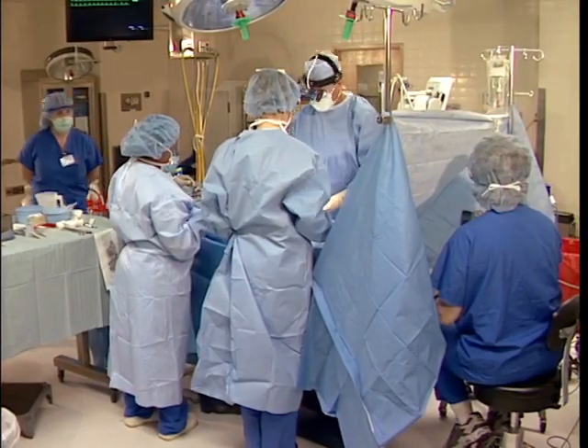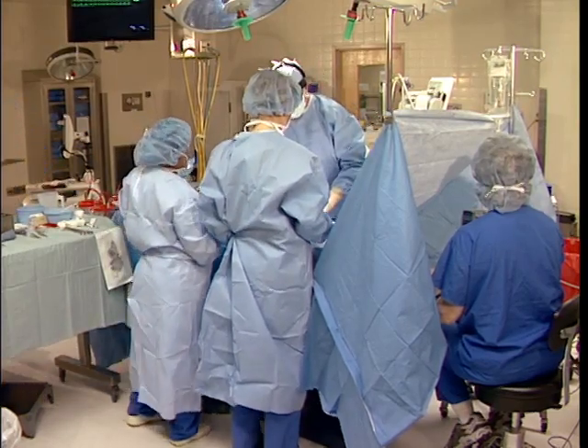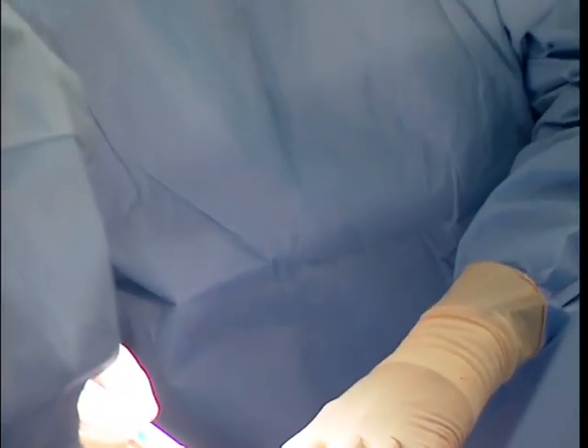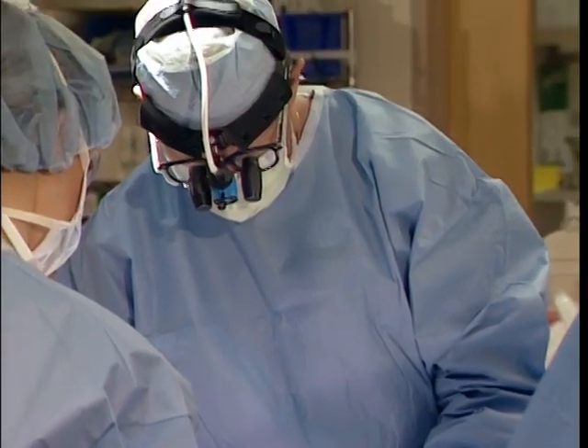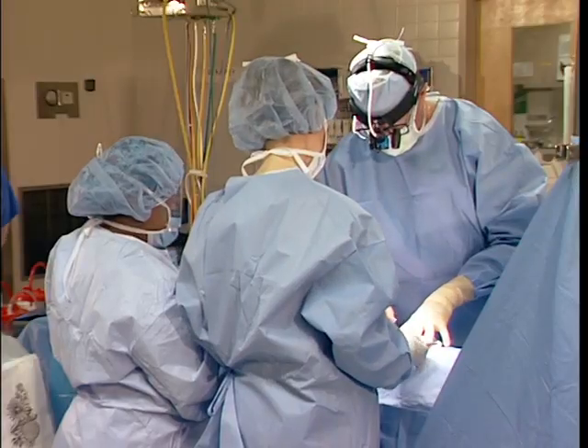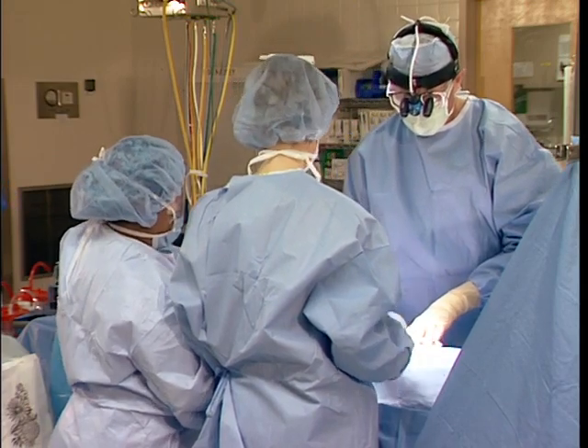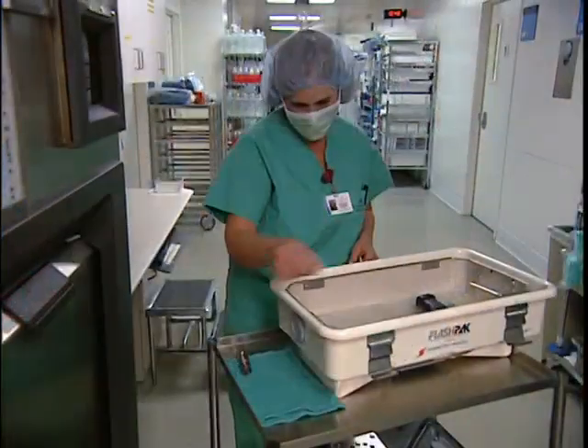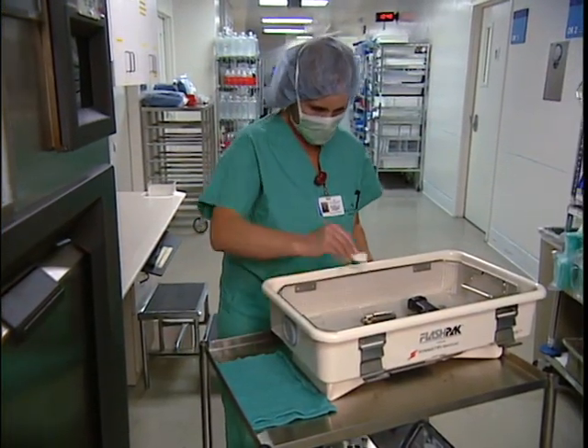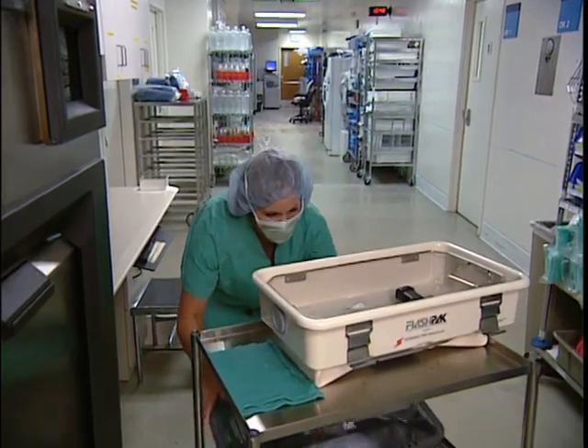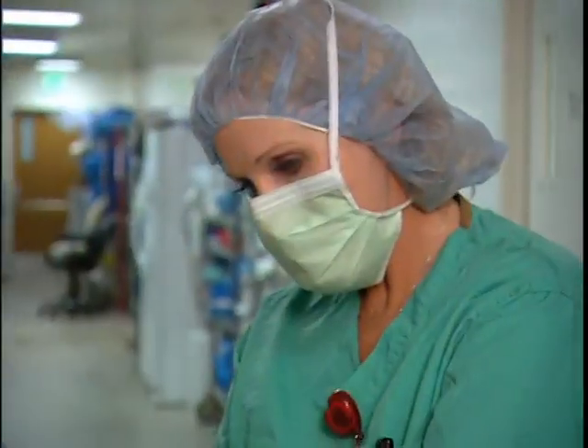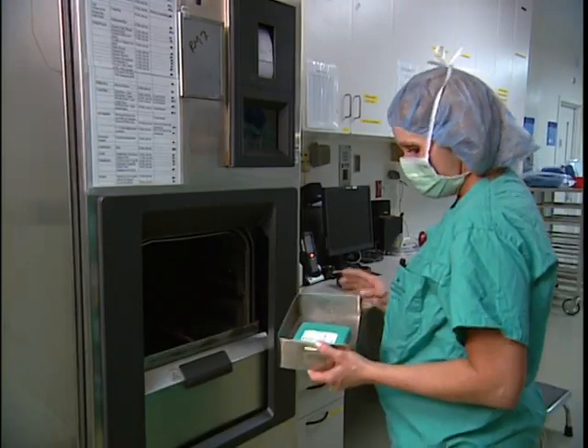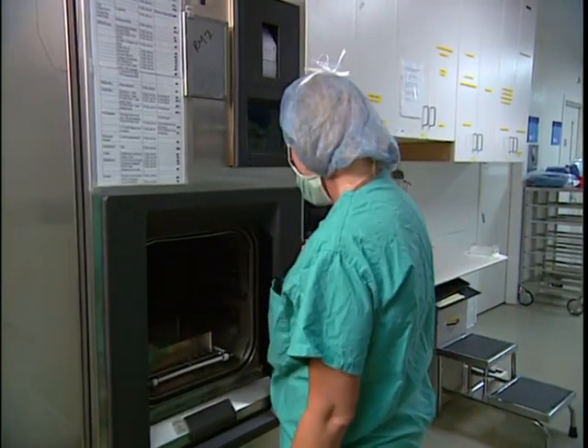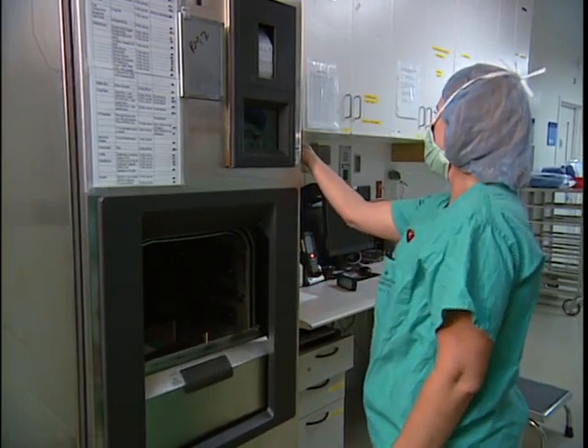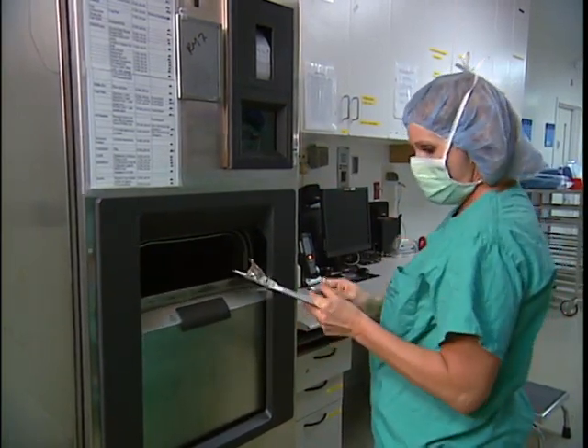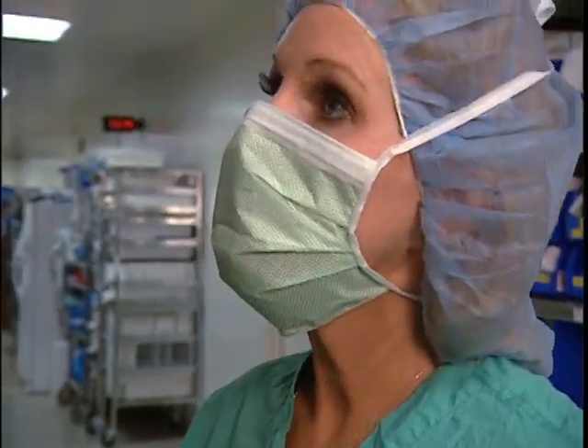In that case, it is important, and in fact it is required, to ensure that the manufacturer of the implant has validated those implants for immediate use steam sterilization, and you must also ensure that you document and monitor the load in accordance with the latest guidelines. When it comes to actually using the immediate use steam sterilizer, make sure the sterilization process takes place in a clean environment. Ensure that the sterilizer is functioning properly by testing it with a biological monitor weekly, preferably daily, according to policy. Quality assurance testing and routine preventative maintenance should be documented.